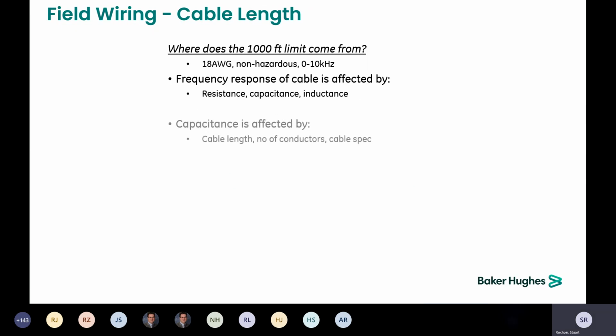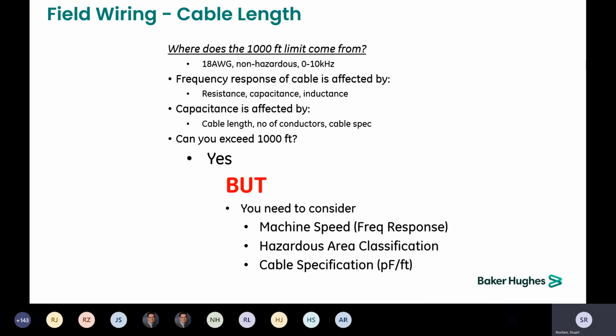Field wiring. With standard wiring, we have a 1,000-foot limit. That is with 18 gauge wire in a non-hazardous environment and looking at a frequency range of 0 to 10,000 hertz, because all of these things affect how the signal degrades through the cable. You can go over 1,000 feet, but we do need to do some calculations with the frequency, hazardous areas classification.